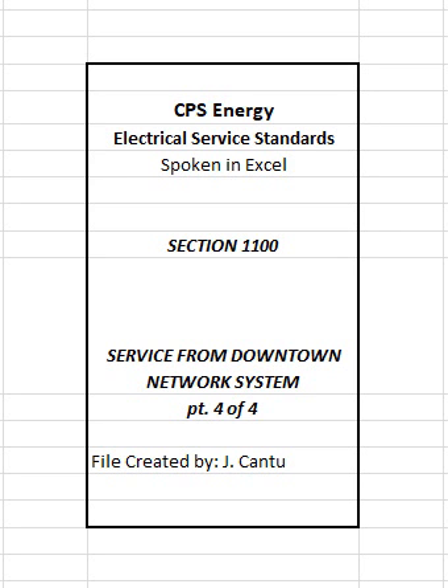1105.1 Coordination of metering design with CPS Energy. Customer shall coordinate with the CPS Energy customer service representative for the review of the metering design by CPS Energy's Electric Service and Metering Standards section prior to ordering any equipment including service equipment to verify metering design will conform to specifications and standards approved by CPS Energy. The following are some basic designs that are allowed by CPS Energy.